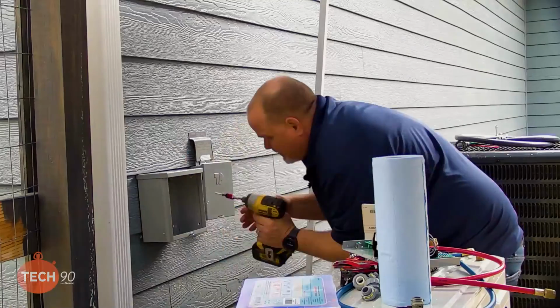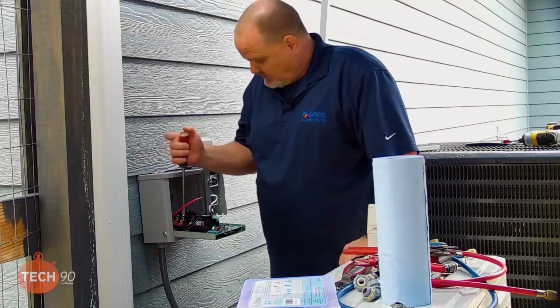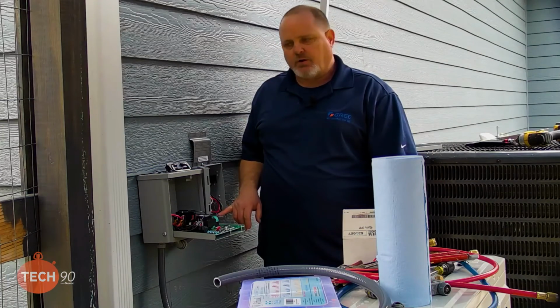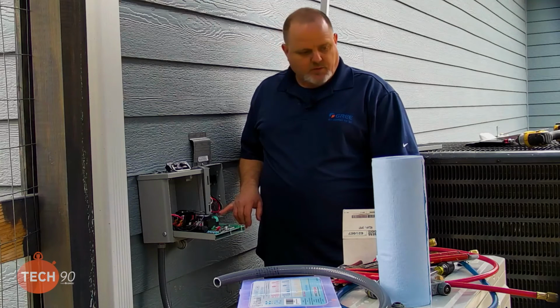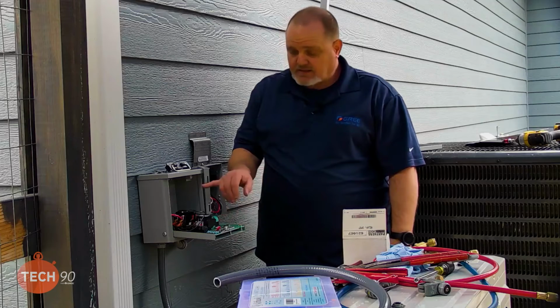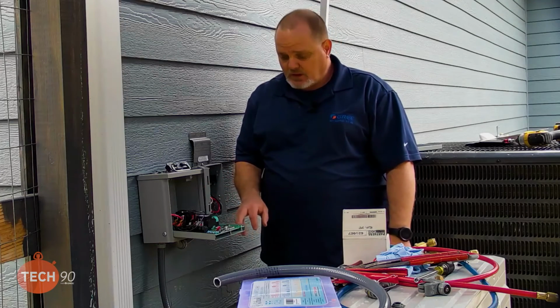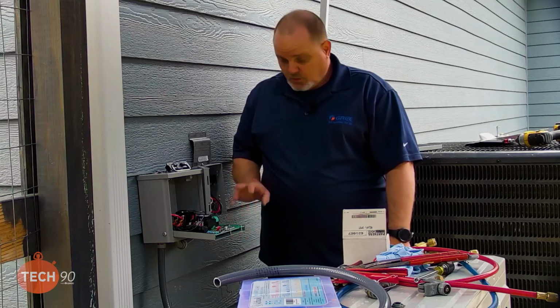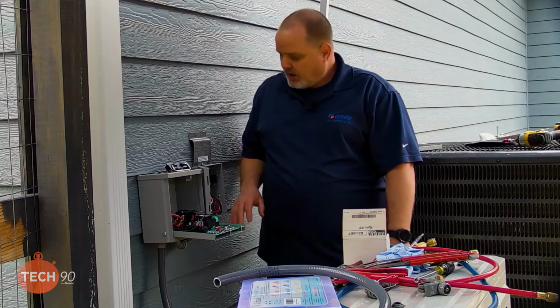We didn't show you the entire installation of the disconnect in ICM 493. So first of all, the electricians had already come out and wired a disconnect and had it set up for us. The breaker's off. The breaker panel's in the garage and the breaker's off to it right now. But anyway, we went ahead and installed the whip going from there to the ICM 493. The ICM 493 is a surge protector along with voltage monitoring, which we will show you the setup of that board. But I wanted you guys to be able to get a view of how this hooks in.